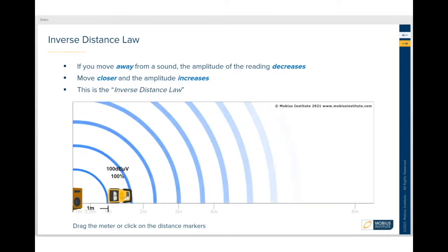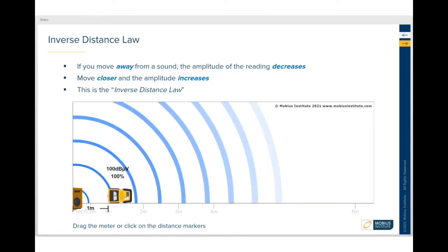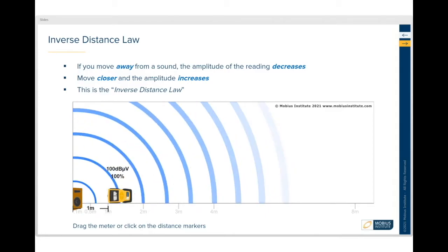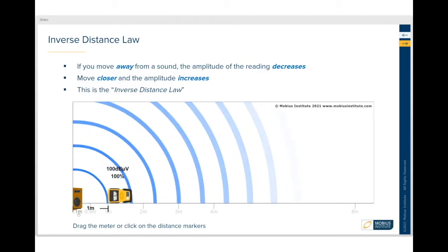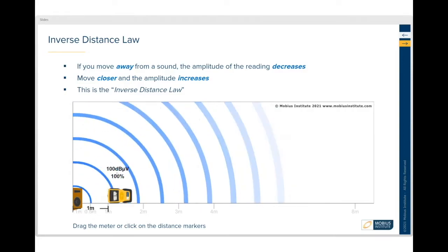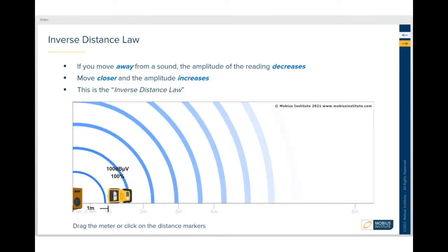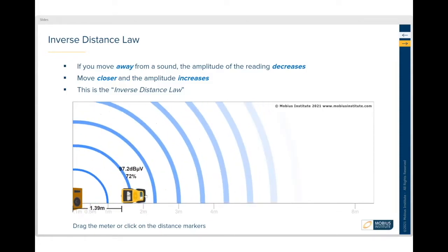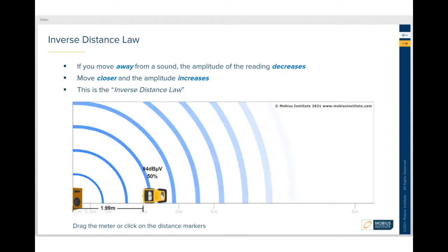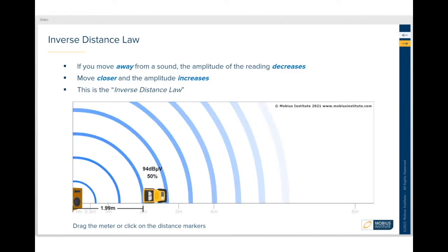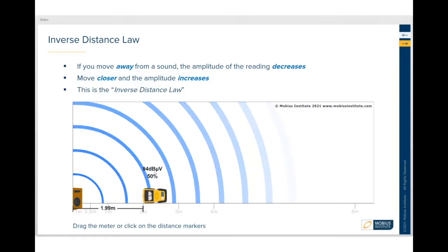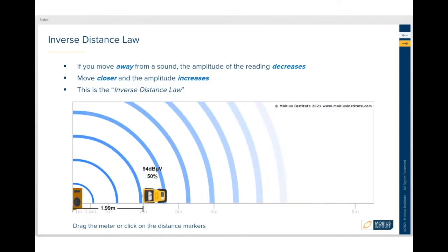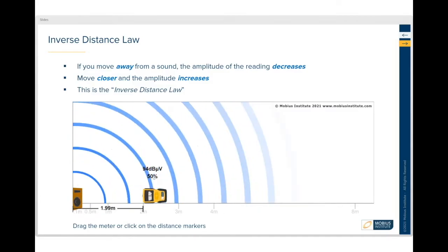Here I have my handy Mobius ultrasound tool that's set one meter from my sound source, my ultrasound source, and you can see the amplitude. As a ratio we're calling that 100%. As I move it out to two meters, you can see the dB value has changed by 6 dB. The value, if we're looking at microvolts, is now half.